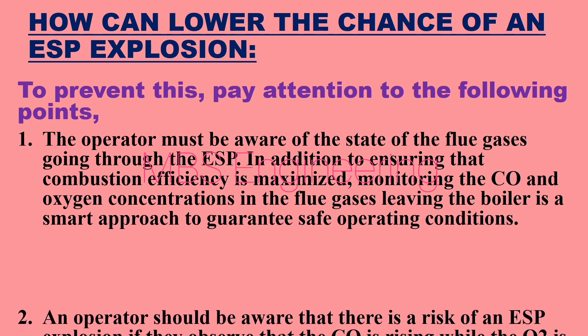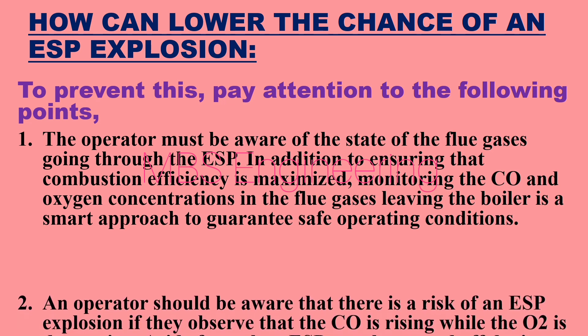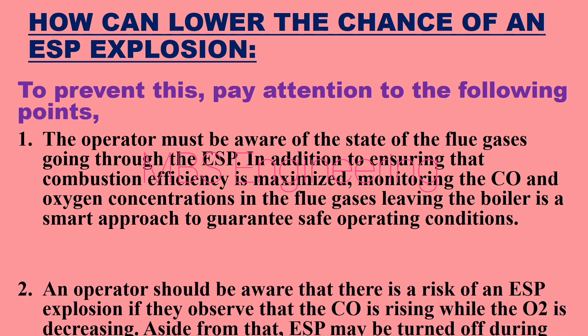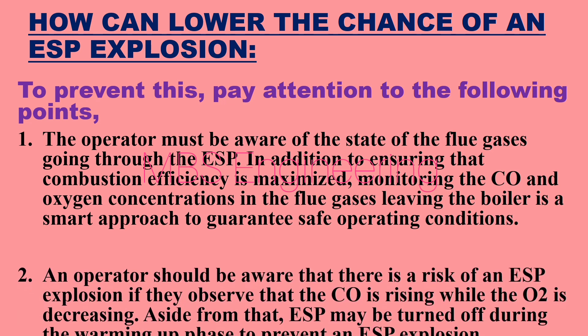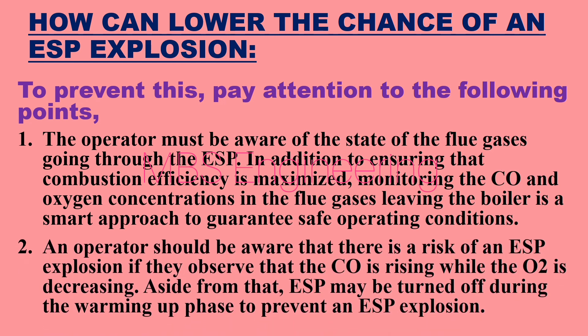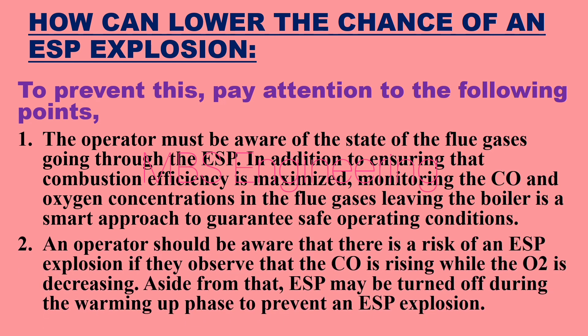Point 2: An operator should be aware that there is a risk of an ESP explosion if they observe that CO is rising while O2 is decreasing. Aside from that, the ESP may be turned off during the warming-up phase to prevent an ESP explosion.